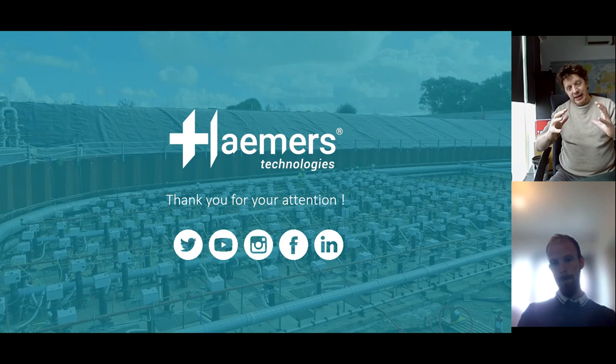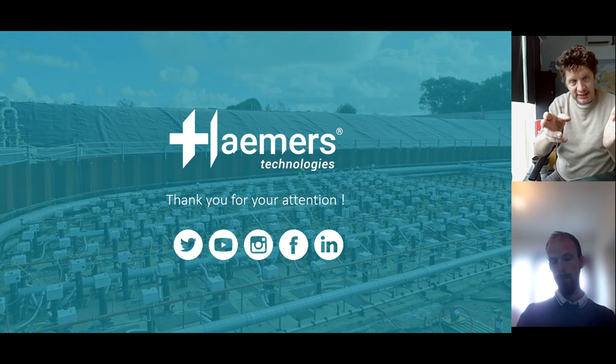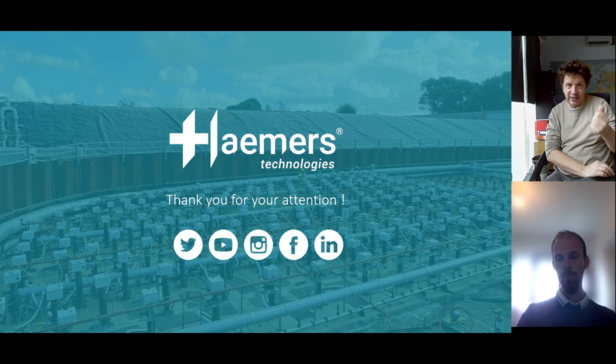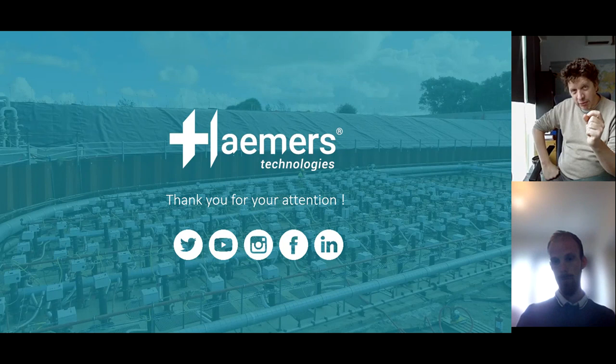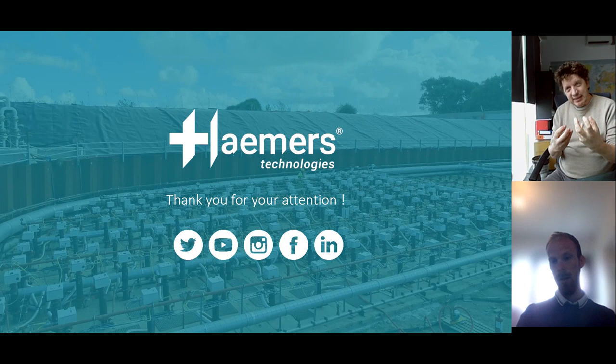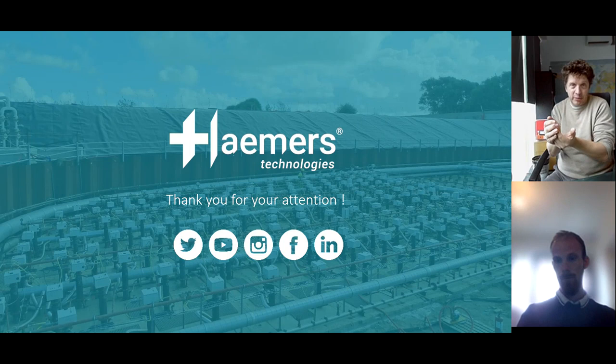And then the second part, just to answer the first part of the question, to add on to that. Yes, when you have a covering layer, the risk is migration up and condensation. Hence the continuity of extraction. Make sure that the blower is always there, so you have a backup for that, and there is a generator in case of an electrical shutdown that continues to extract and to keep everything under negative air. But also very important is to note where the difference in permeability and humidity is, and temperature. The top part has lower permeability, has of course more moisture.